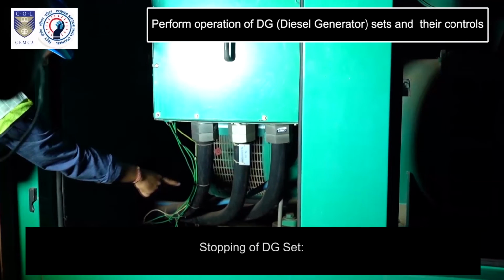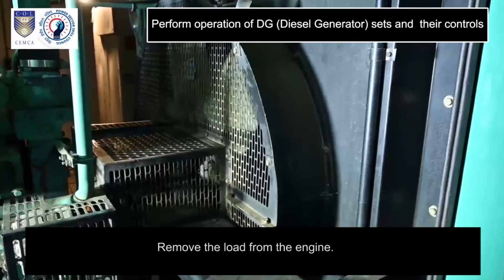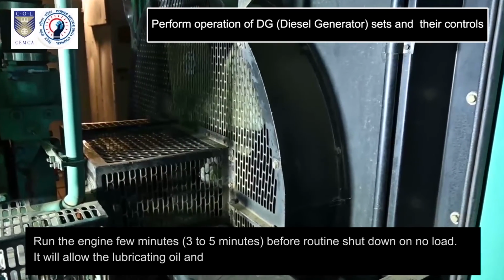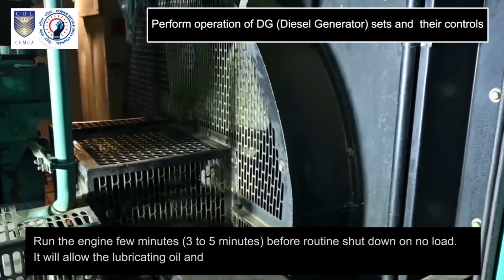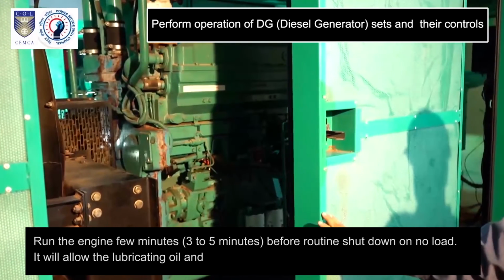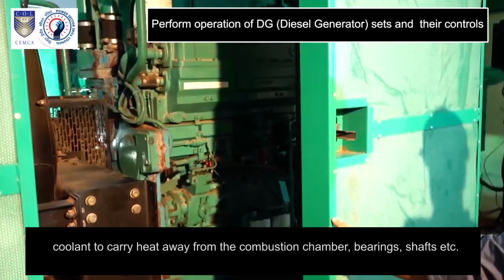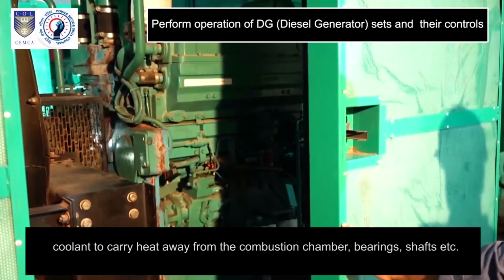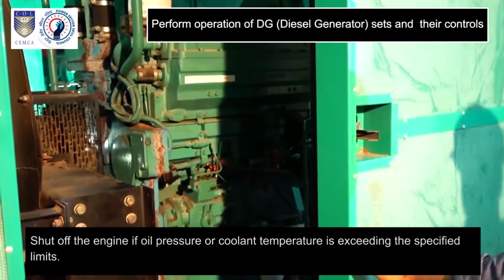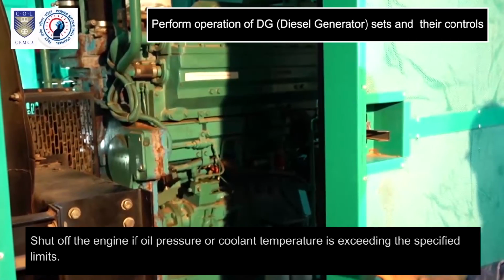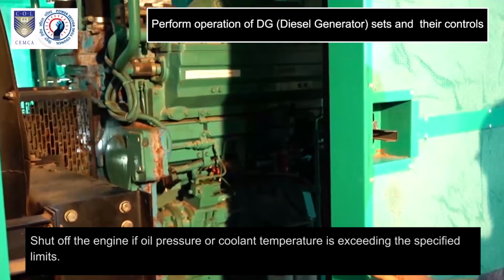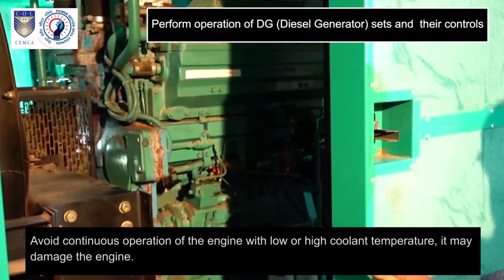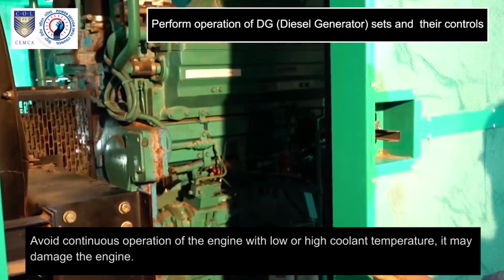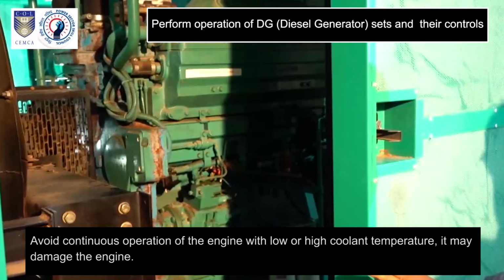Stopping of the DG set. Remove the load from the engine. Run the engine for a few minutes, 3 to 5 minutes, on no load before routine shutdown. It will allow the lubricating oil and coolant to carry heat away from the combustion chamber, bearings, shafts, etc. Shut off the engine if oil pressure or coolant temperature exceeds the specified limits. Avoid continuous operation of the engine with low or high coolant temperature. It may damage the engine.